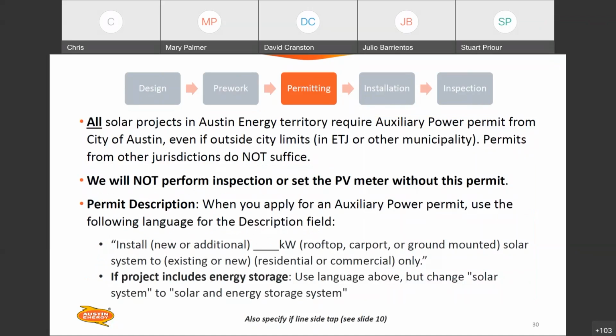To cover a question from earlier: all solar projects in Austin Energy territory require an auxiliary power permit from the city of Austin. Even if your project is outside city limits, it still requires a city of Austin electrical permit, regardless of whether you also have to pull a permit from another jurisdiction like the city of Pflugerville or Travis County. The city of Austin permit is required in addition to those. We will not perform inspection or set the PV meter without that city of Austin auxiliary power permit.